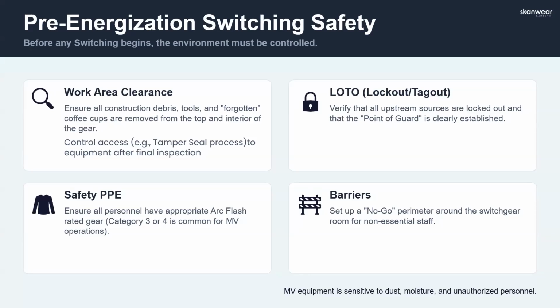What does your lockout tagout look like? Is it established? Is it clear? Does everyone understand that? What PPE is necessary for the energization? Obviously, you're going to have workers who go in after that energization to watch phase rotation and proper voltages. So they need to be dressed out in whatever category the incident energy has it. And then are your barricades in place and effective, right? With the proper clearances based off of the incident energy. Next slide.